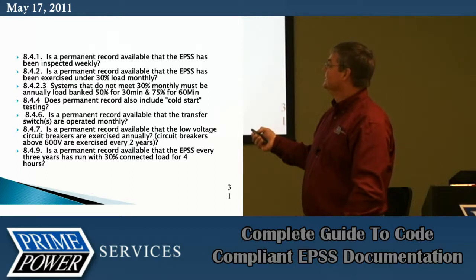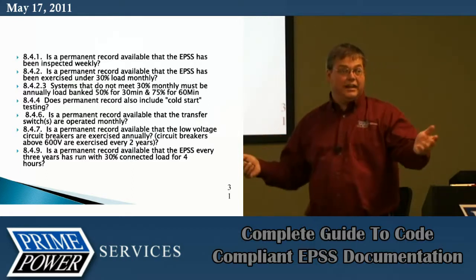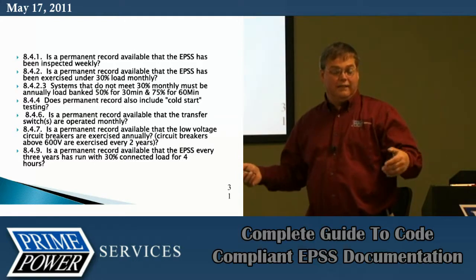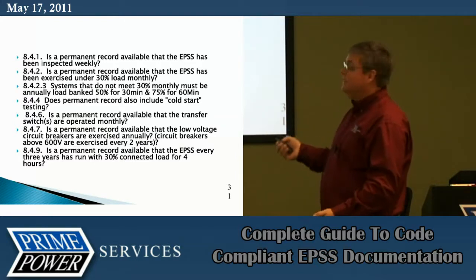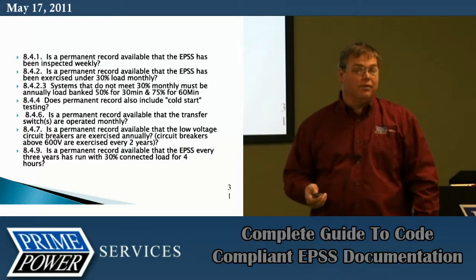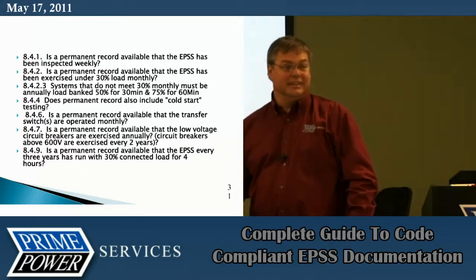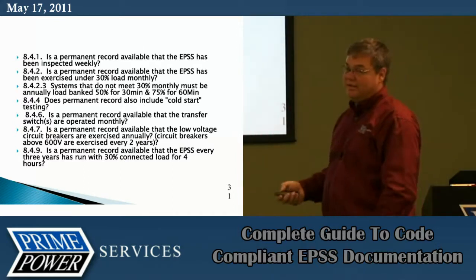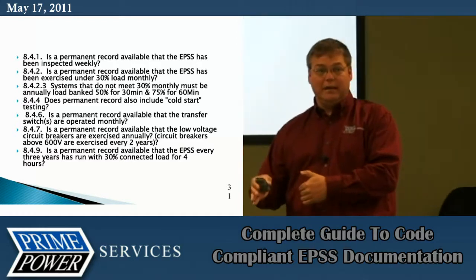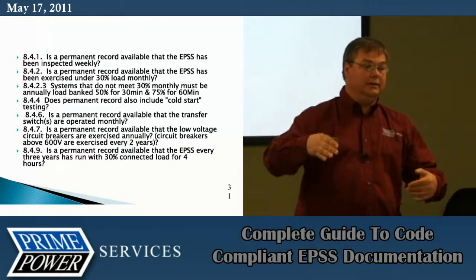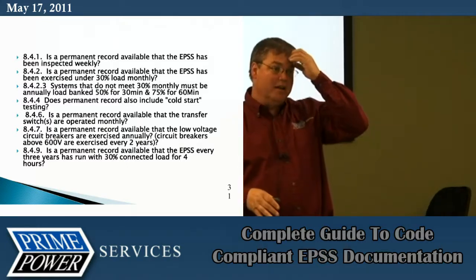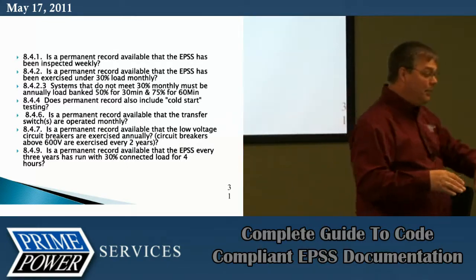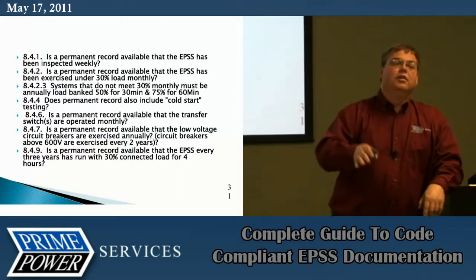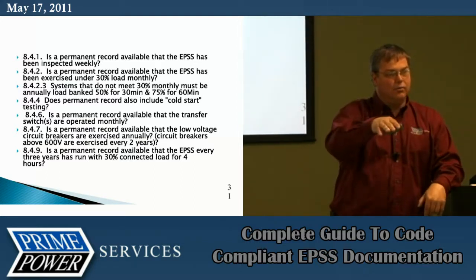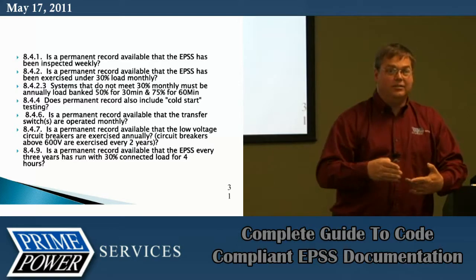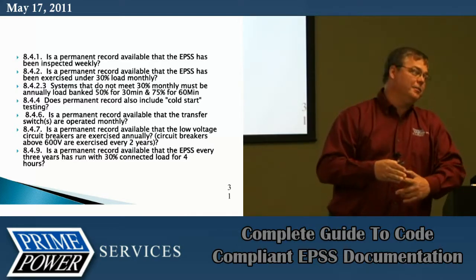That's not for 2 hours, right? For the 2 hours, your annual test is required to be 2 hours. And when you read the verbiage, it says 25, 50, and 75%. But what's wrong with that if you want to use it for a monthly run? Not 30, it's not 30. I don't know why NFPA they say 25% on a load bank. The idea was so you could start it up and let it build up, and that makes sense. But it only applies if you want to use that run for another test. Just be careful - all your load banks, as a recommendation, should start at 30%.